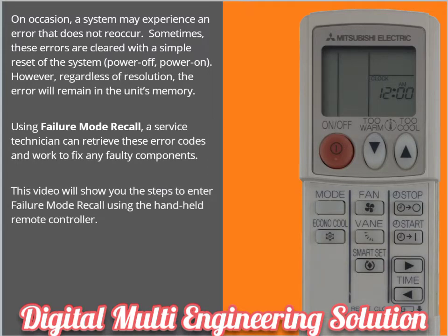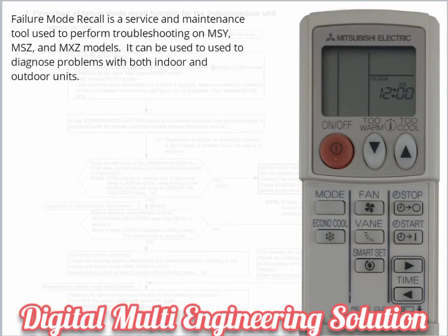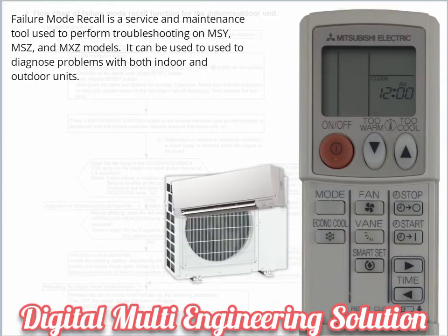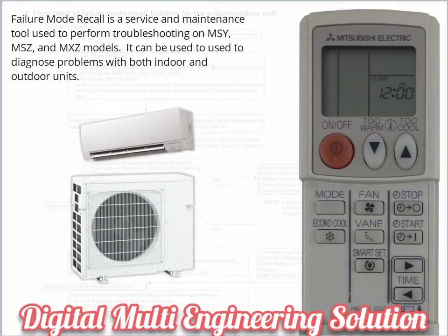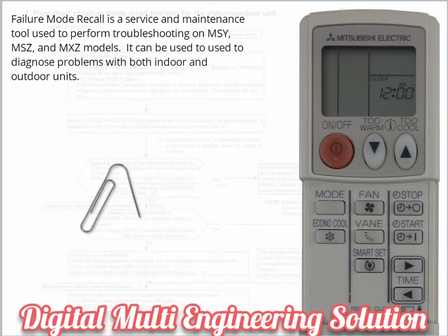This video will show you the steps to enter Failure Mode Recall using the handheld remote controller. Failure Mode Recall is a service and maintenance tool used to perform troubleshooting on MSY, MSZ, and MXZ models. It can be used to diagnose problems with both indoor and outdoor units. Before accessing Failure Mode Recall, you will need to obtain a paperclip or similar pointy object.